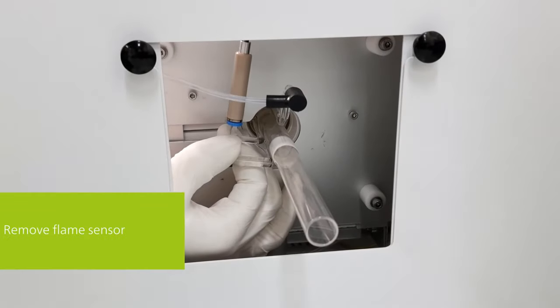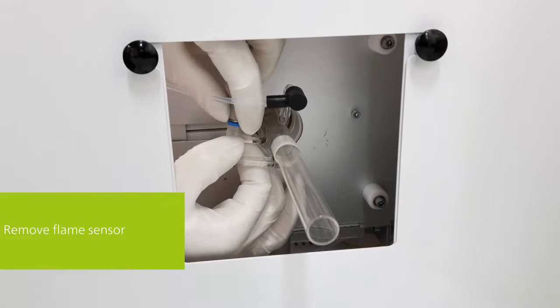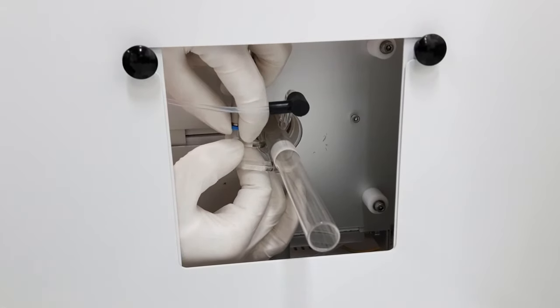In a third step, remove the connections for the water, carrier gas as well as the flame sensor. Here, you need to be careful to stabilize the fragile quartz parts.